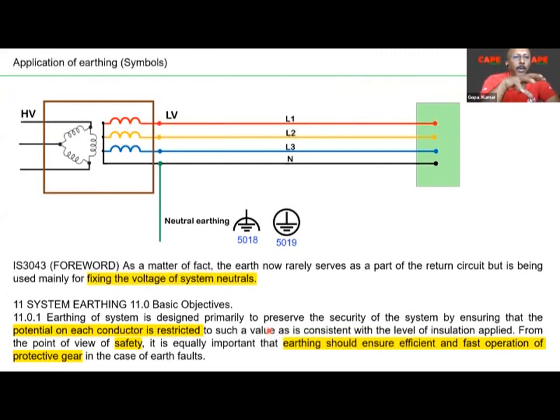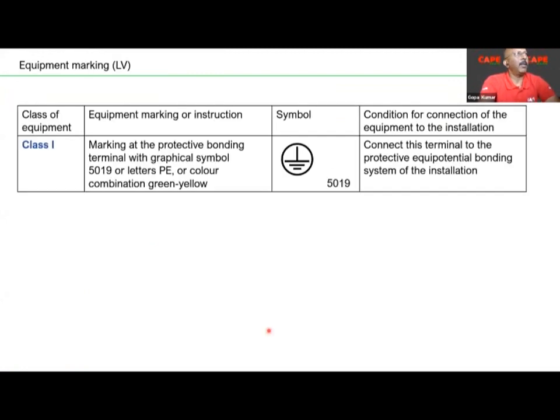Now, this is what is required in a source. What is required in an equipment? First, we should understand what kinds of equipment there are. Equipment is classified into class 1, class 2, and class 3. Class 1 is equipment whose body, for example a motor or a panel board, will experience a voltage during an earth fault. It is denoted by either the number 5019, the letters PE, or the color combination green and yellow. Basically, class 1 equipment has to have a terminal marked in this way, or with the symbol 5019. What does it mean? Connect this terminal to the protective equipotential bonding system of the installation.